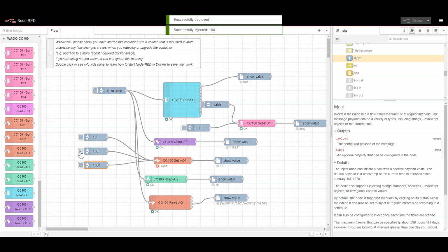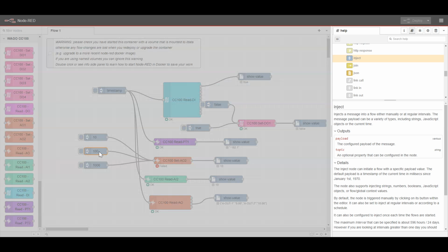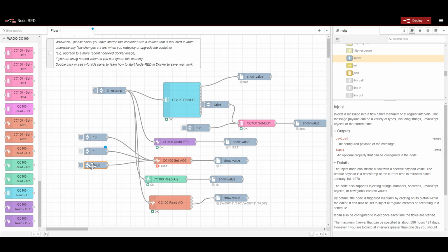And just for example, I'm sending the command to the AO card, and then we are reading it over the analog input. As I have looped it, we can do the same thing. It supports 0 to 10 volts, so we have to give the command from 0 to 10, not the counts, but basically from 0 to 10, for the AO. Like that, we can read the data.